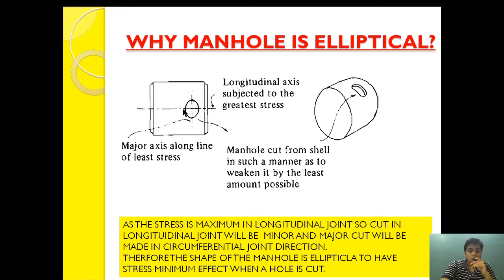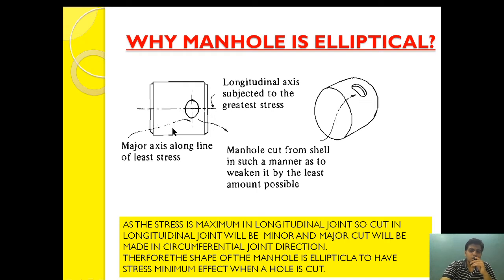To avoid crack development or to avoid larger stress acting on a boiler shell, the doors are cut elliptical. The major axis is in the circumferential direction and the minor axis is in the longitudinal direction. Since the stress is maximum in the longitudinal joint, the cut in the longitudinal joint direction will be minor, and the major cut will be made in the circumferential joint direction.